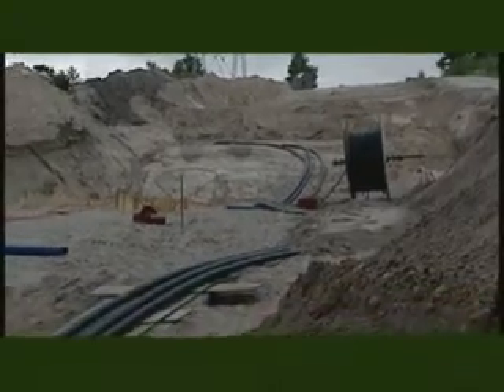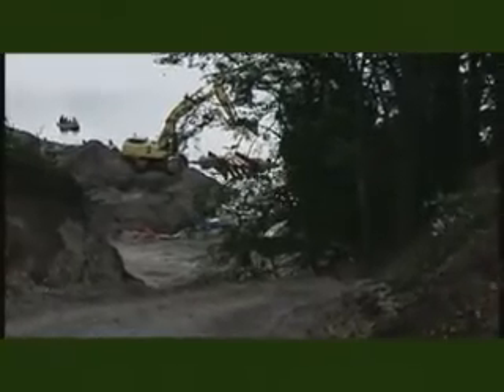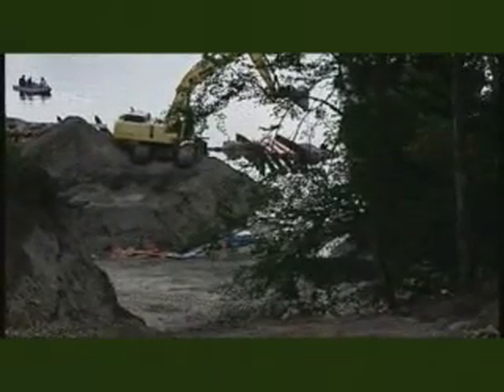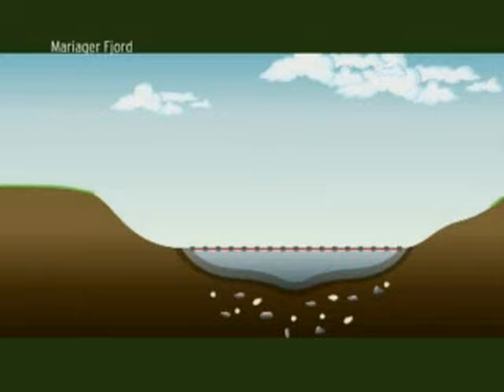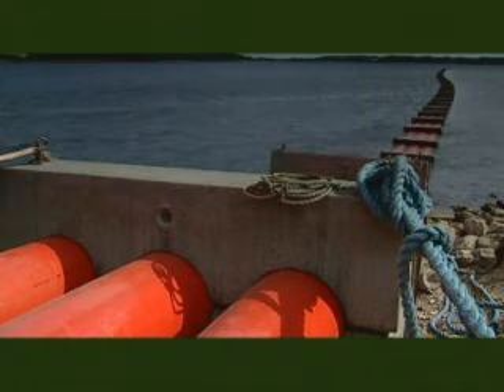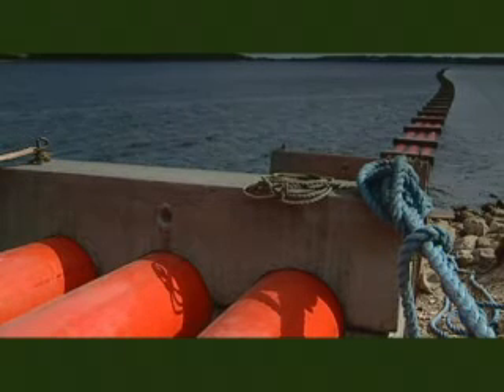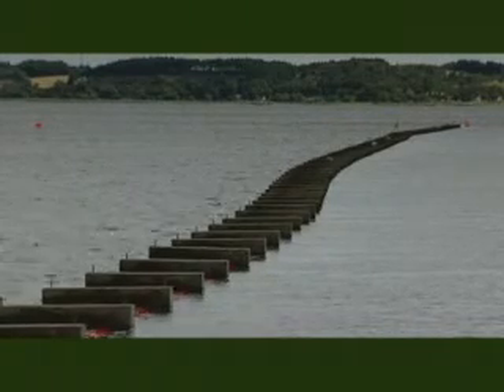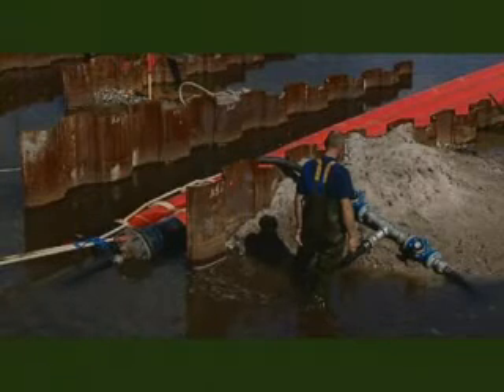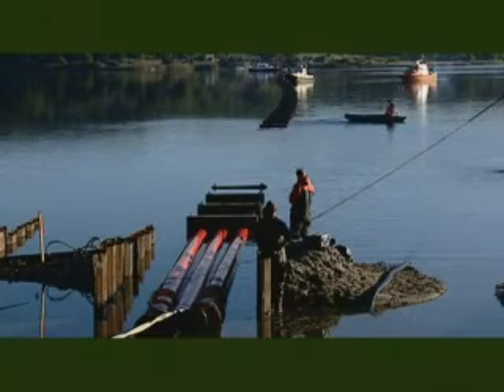The tender for the cabling work did not specify a particular solution as to how the cable should be laid across the inlet. Of the various alternatives, it was decided to opt for a technically straightforward solution, which was both financially and environmentally the most attractive. The solution involves sinking pipes onto the floor of Mariager Fjord. The pipes were joined together in sets of 3 using ballast blocks. The size and weight of the ballast blocks and the spacing between them was determined so that the pipes and the ballast blocks remained buoyant on the surface until they were towed into place. By filling the middle pipe with water, the pipe system sank to the floor of the inlet. The entire operation involved making 3 pipe rafts.